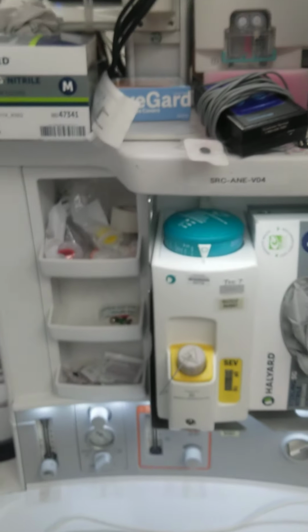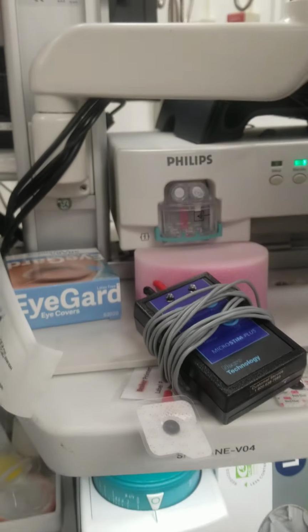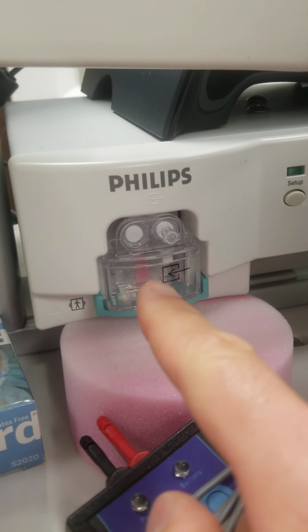So again, okay, we're missing something. I like everything that's going to be on the patient to go through these circuit checks, because if you do have a leak, you're going to know. And if the leak is because the CO2 housing right here has a crack in it, how would you know? You would never know. And you might be able to see on the CO2 waveform that the waveform was off, right?